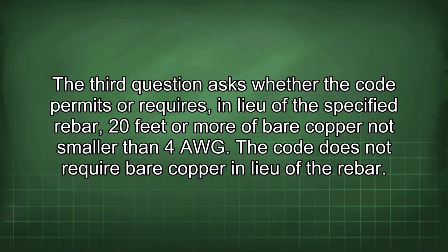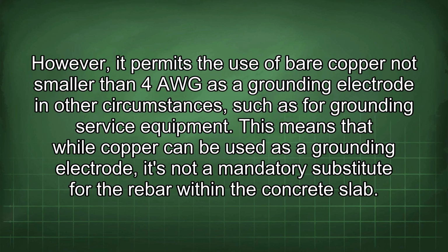The third question asks whether the code permits or requires, in lieu of the specified rebar, 20 feet or more of bare copper not smaller than 4 AWG. The code does not require bare copper in lieu of the rebar. However, it permits the use of bare copper not smaller than 4 AWG as a grounding electrode in other circumstances, such as for grounding service equipment.